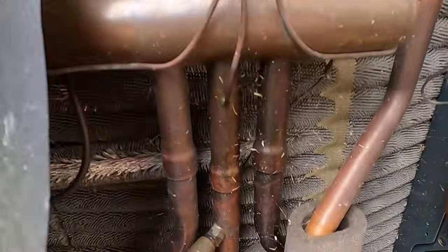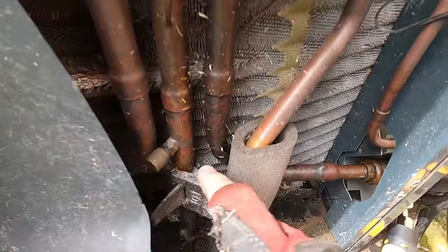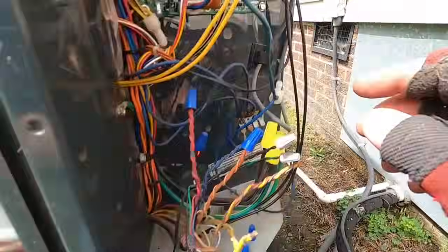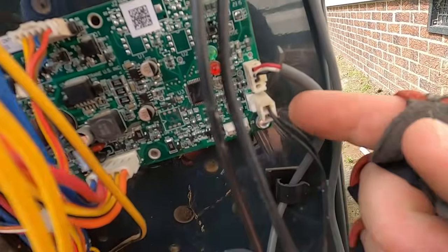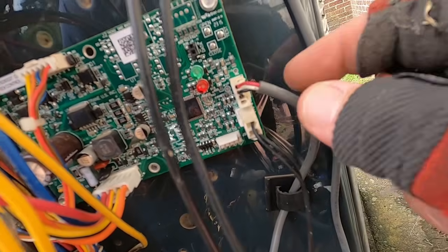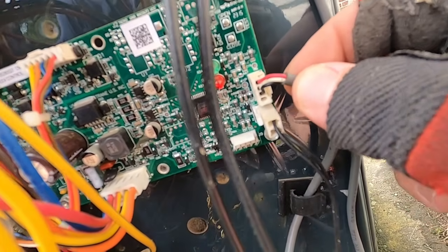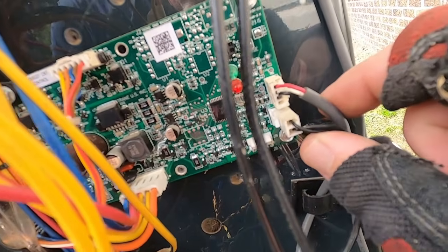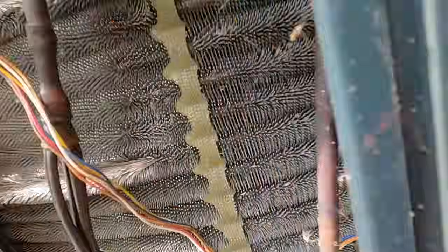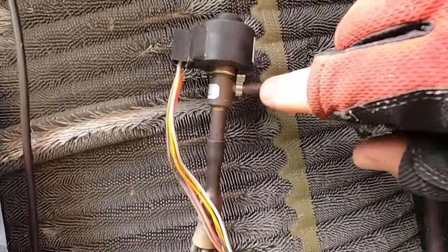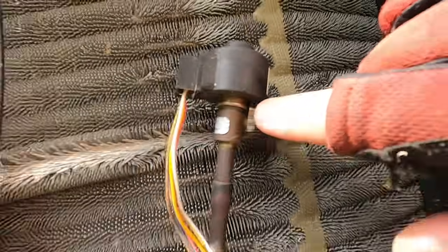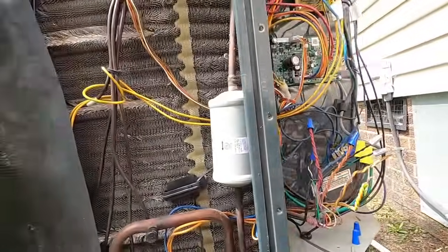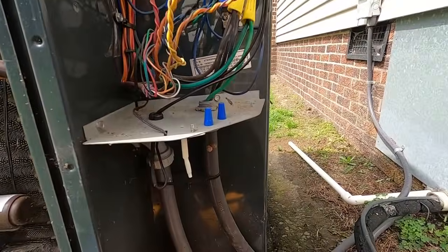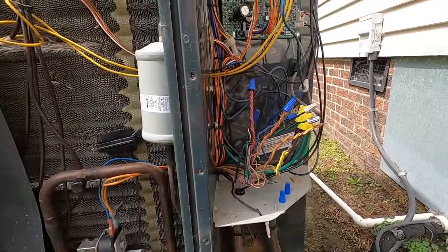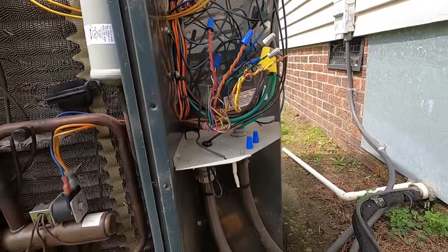So there's your suction line temperature sensor there. Comes back up through here, plugs to this board. So it's reading the suction line temperature, and then it's reading your suction pressure, correlating that to a temperature, reading superheat from those 2 points, regulating your stepper motor. Here's that other stepper motor that clips on the bottom, and then regulating your refrigerant flow in heat mode. But she's back on and running.